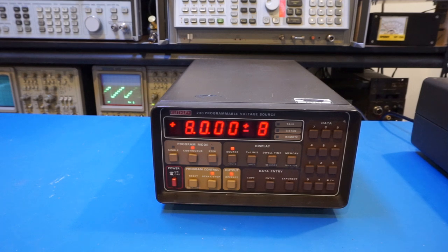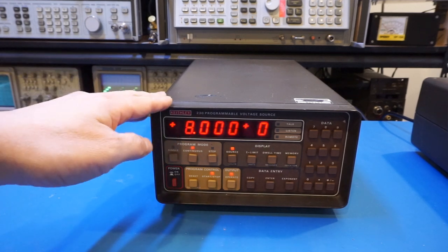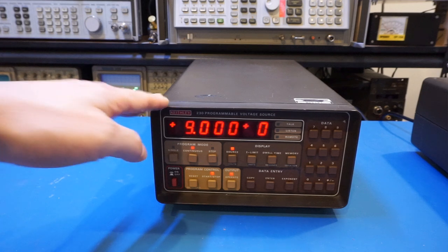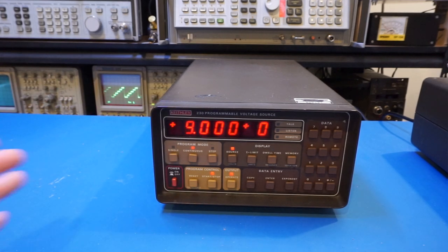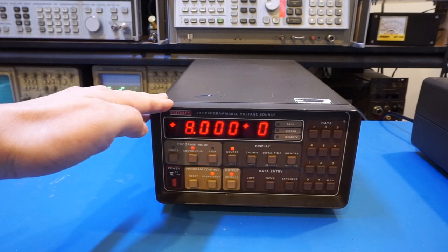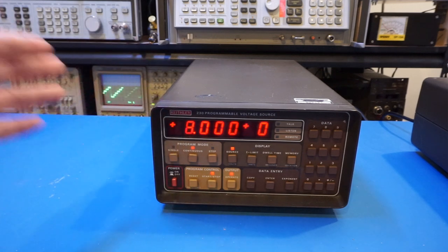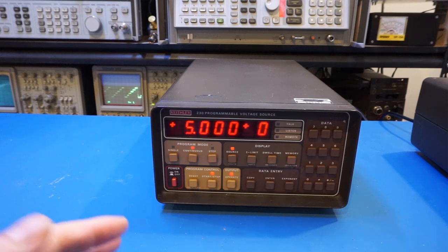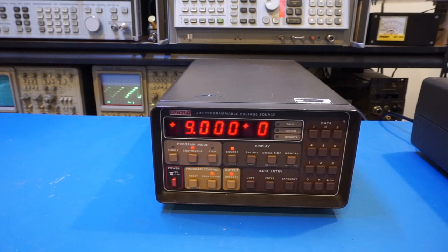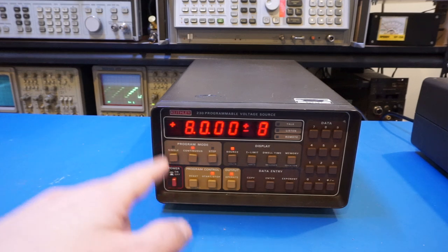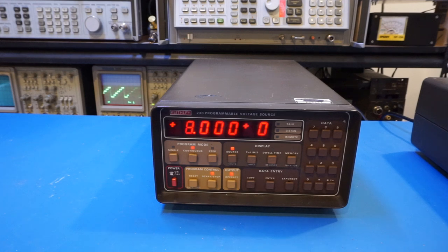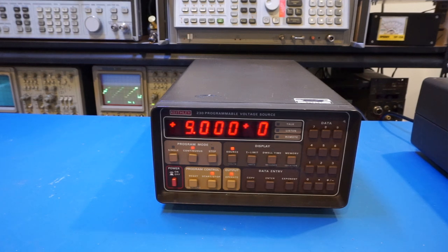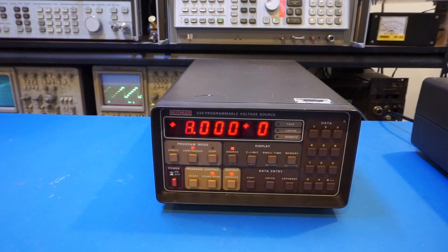Now, as you can see, we indeed can use this programmable voltage source to do a lot of different things. Now, it's a pity that it doesn't have an onboard battery to permanently store these waveforms. As you saw earlier, entering these are non-trivial and sometimes you make mistakes. Of course, you can always go back, use a single step to verify each step. But nevertheless, as soon as it powers off, all the memory settings are going to be erased. So that's something to remember about this instrument here.